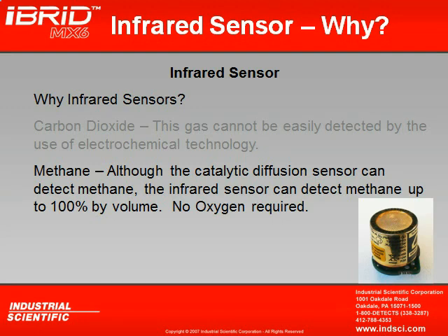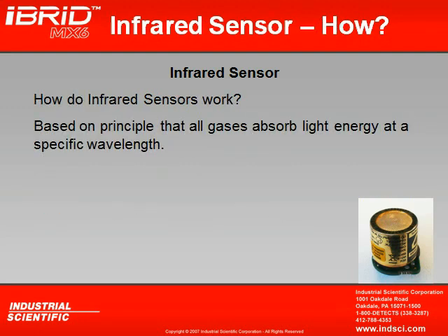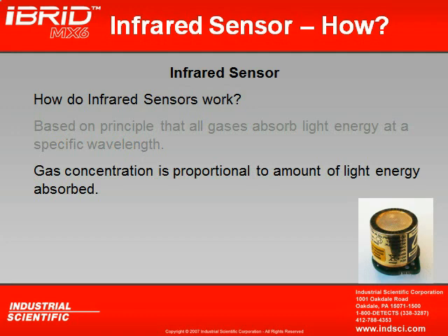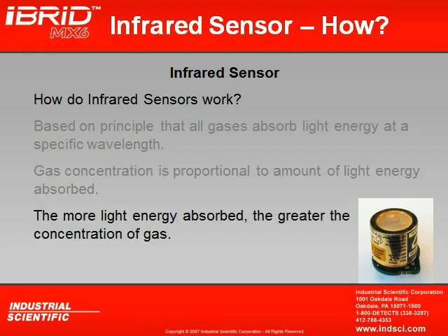So basically, how do these sensors work? Well, they're based on the principle that all gases absorb light energy, and they're going to absorb this light energy at a specific wavelength. If we know what this wavelength is, we can look for the absorption of gas out on that spectrum. And gas concentration is proportional to the amount of light energy absorbed. The more of that light energy absorbed, the greater the gas concentration.